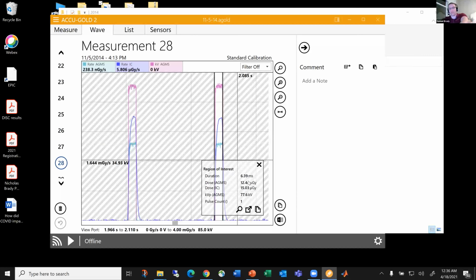But I'm verifying that it's actually pretty small or thin. Pulse width is thin, so that as I develop this setting for a pediatric patient or an extremity, I get good resolution. And if you're going in there and you stack 20 centimeters or 30 centimeters of PMMA, and now your pulse width is really, really wide, now you can see if there are other ways to adjust.